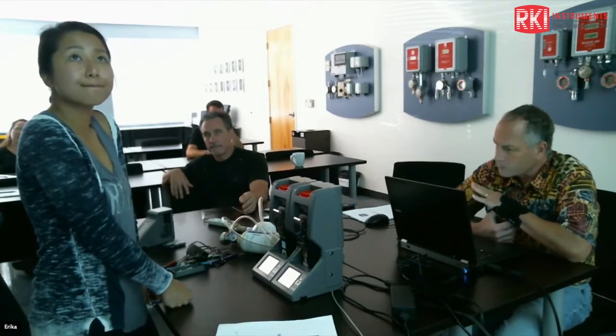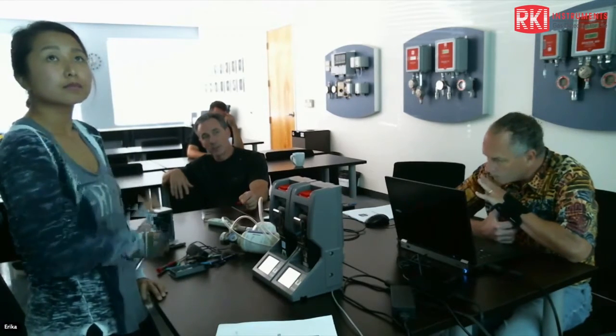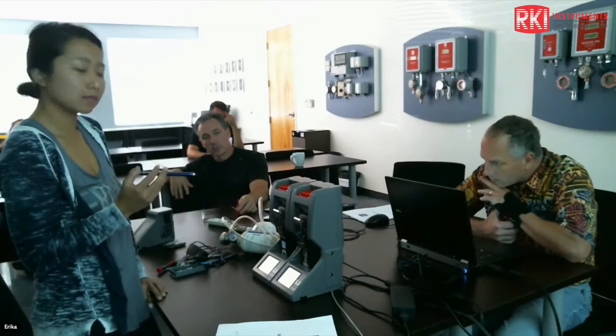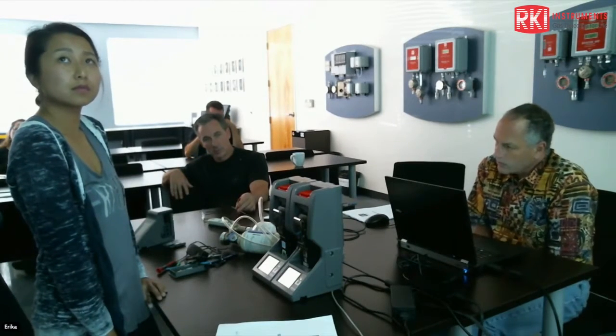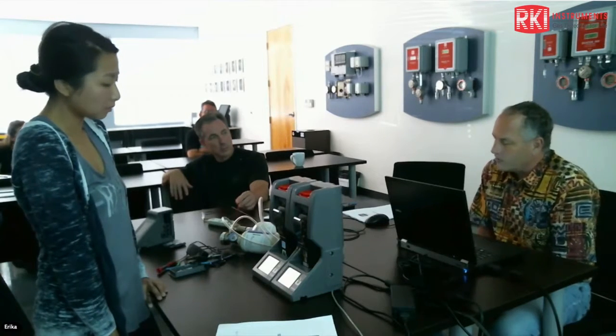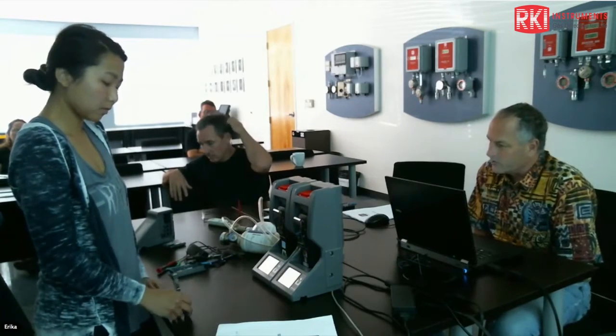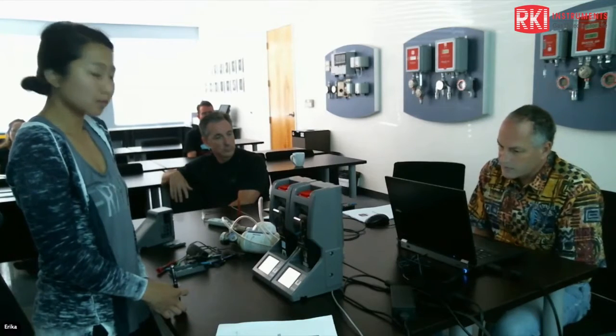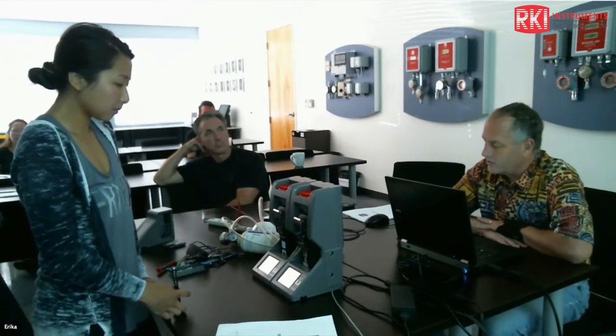Yeah, I have it set for just 4 gas, and I was surprised that it did bump the PID, because in the software of the unit, I just have it as a 4 gas, not all. You know, you can choose either 4 gas or all, and I chose just 4 gas. Right. And I was surprised. That setting only affects whether the cal date or bump date is reset. It doesn't disable bumping or calibrating those other sensors. It just says that the reset of the date is not dependent on those being bumped or calibrated. I got you. Okay. So you must have a 5 gas cylinder then.